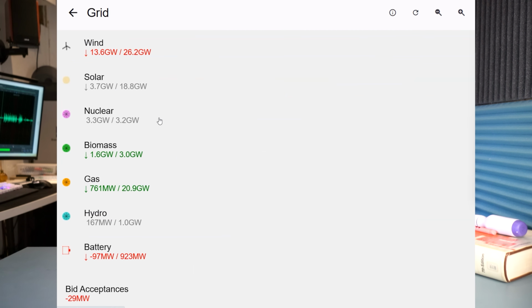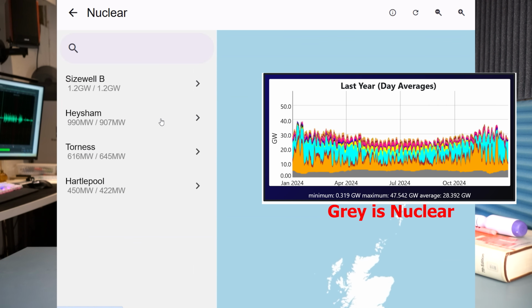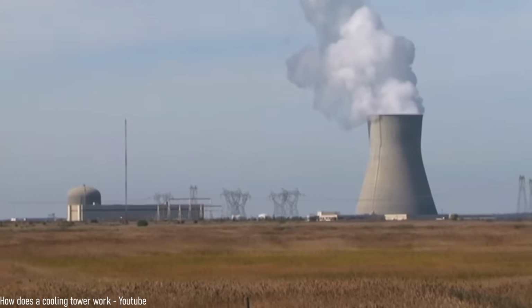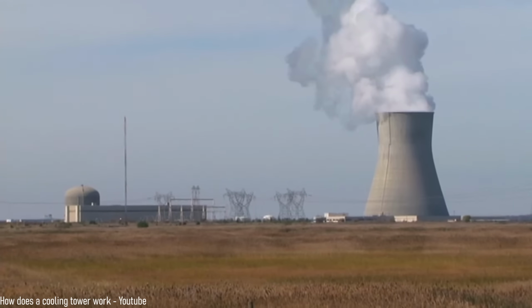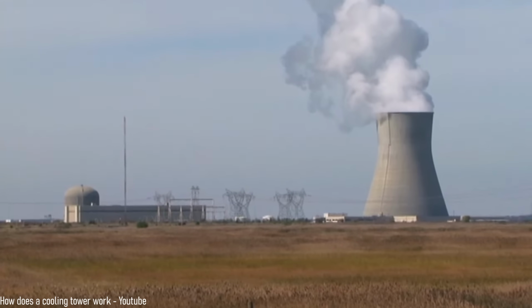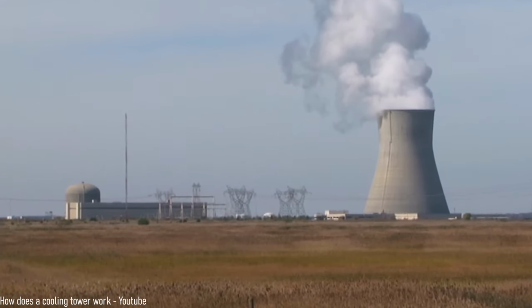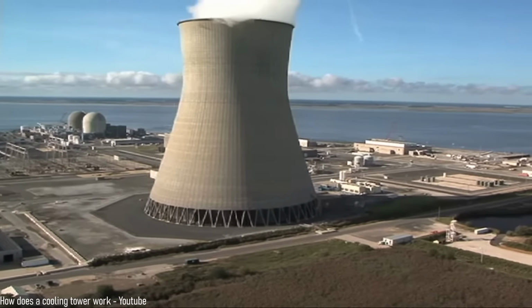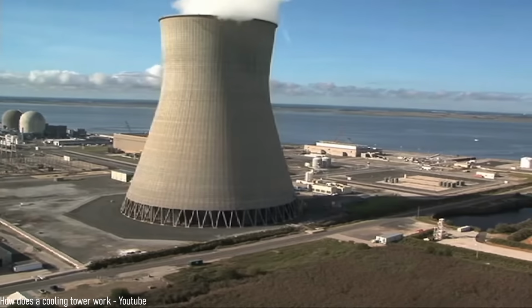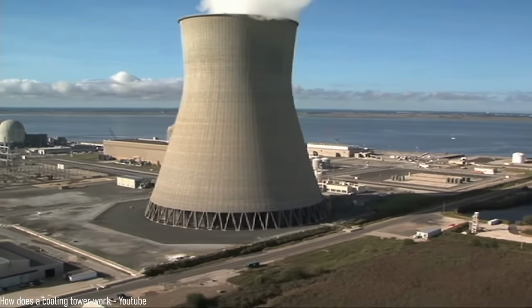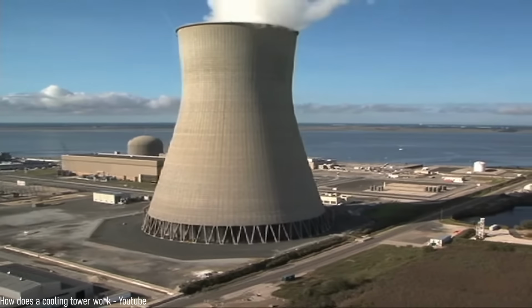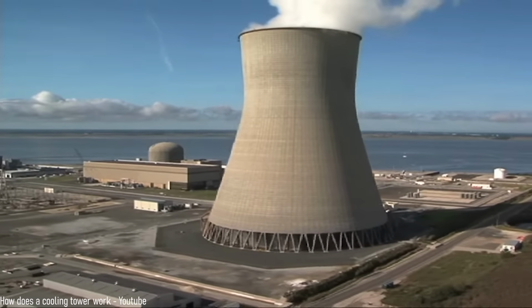But you might be thinking, well, they're usually on, providing a nice stable base load constantly. And you're right. If a blackout happens, they'll likely keep running without much issue, and the backup generators will just make sure the pumps keep running. But they can't typically cold start without the grid, so don't count. It will, however, be used to great effect during the restoration by providing lots of good stable frequency and power, acting as an anchor, if it remains connected to its own little energy island in the grid.